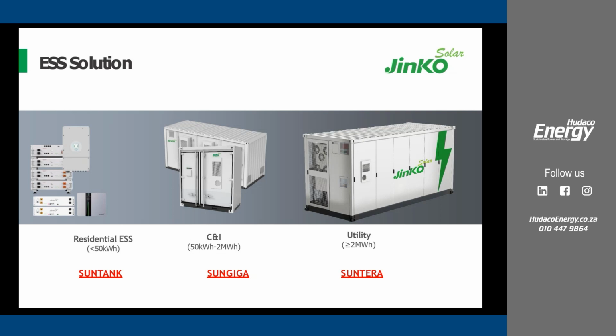For the indoor scenarios, we have basically between less than 2 megawatt hours and more than 50 kilowatt hours - that's our classification. Though in other customized scenarios, we can get up to 6.4 megawatt hours and up to 2 megawatts of PCS for standard solutions.